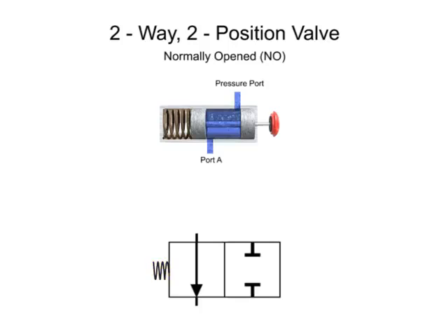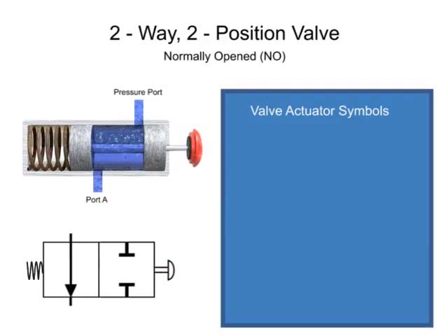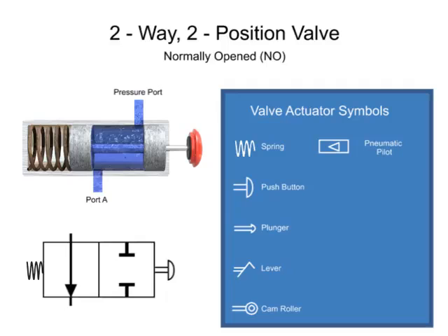Actuators used to change valve positions can be mechanical, pneumatic pilot, or electric solenoid. To complete the diagram, the primary actuator symbol is placed on the other end of the graphic symbol. In this case, the actuator is a push button. Mechanical actuators change valve positions with springs, push buttons, plungers, levers, and cam rollers. Pneumatic pilots change valve position with a pressurized air signal. Electric solenoids that change valve positions by directly moving the valve element are called direct solenoids. Electric solenoids that open small pilot valves and allow pressurized air to move the valve element are called solenoid controlled pilot operators.